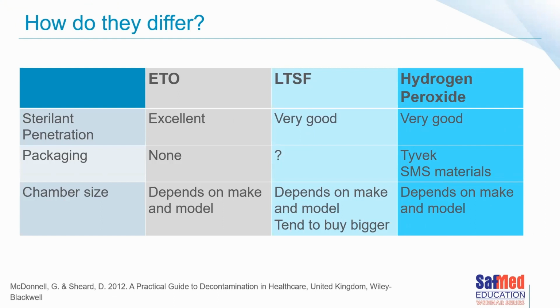The sterilant penetration, to be honest, the best form of sterilant penetration is with ethylene oxide. Low temperature steam formaldehyde and hydrogen peroxide are also very, very good. Packaging nuances, there are slight differences in terms of what consumables you can use and what type of packaging you can use for the three different types of sterilants. The chamber size, again, will depend, needless to say, on the make and the model. We tend to buy the low temperature steam formaldehyde as a bit bigger because we use them as autoclaves as well.